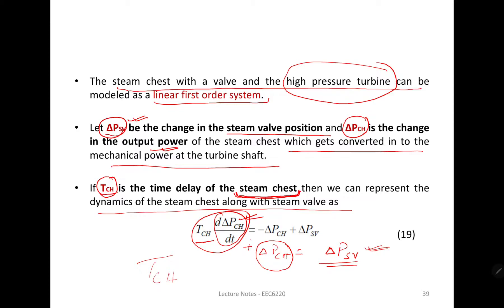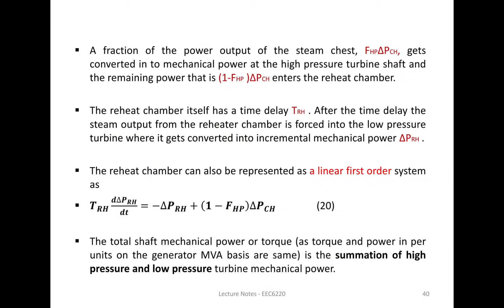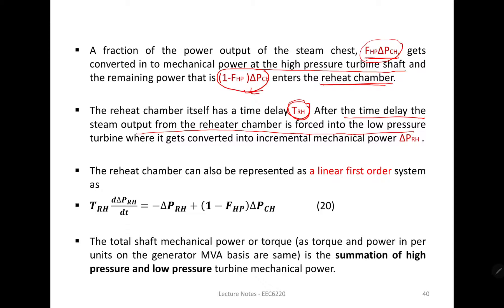The fraction of the power output from the steam chest converted into mechanical power at the high pressure turbine is FHP times delta PCH. The remaining steam that does not get converted at the high pressure turbine goes into the reheat chamber. The reheat chamber itself is modeled as a time delay TRH — the time delay of the reheat chamber.